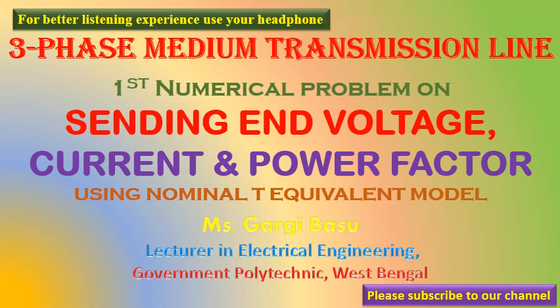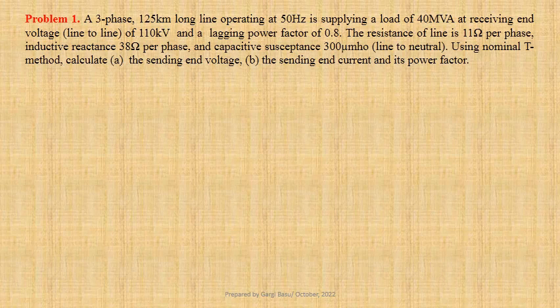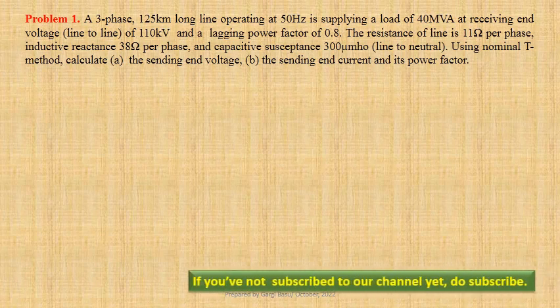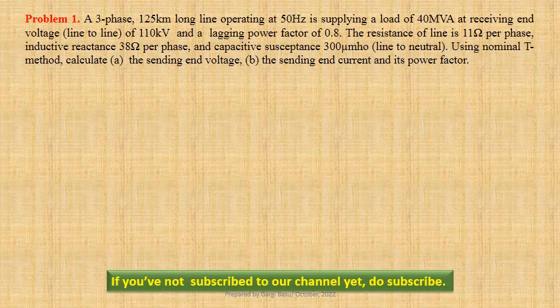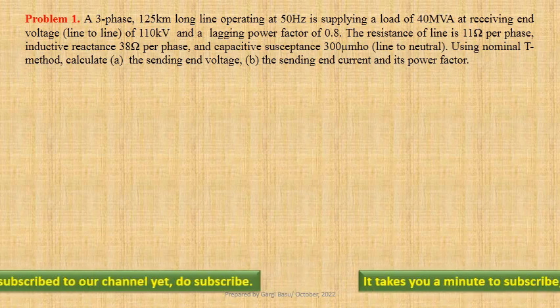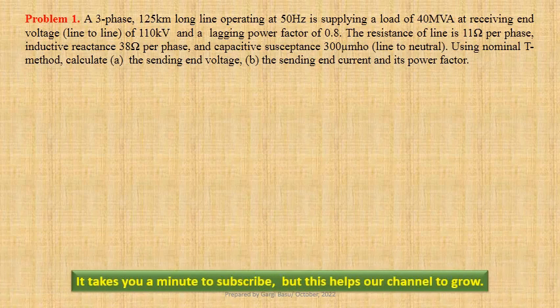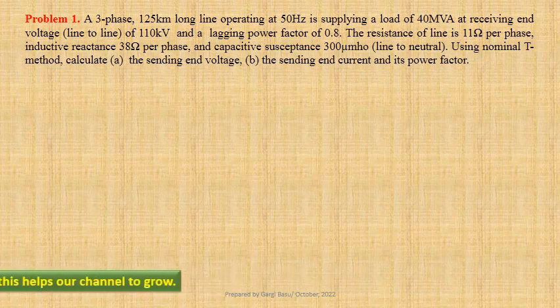A three-phase 125-kilometer long line operating at 50 Hz is supplying a load of 40 megavolt ampere at the receiving end with a lagging power factor of 0.8. The line-to-line receiving end voltage is 110 kilovolts. The resistance of the line is 11 ohm per phase, inductive reactance 38 ohm per phase, and capacitive susceptance 300 micromho line-to-neutral. Using the nominal T-method, we have to determine the sending end voltage, the sending end current, and its power factor.